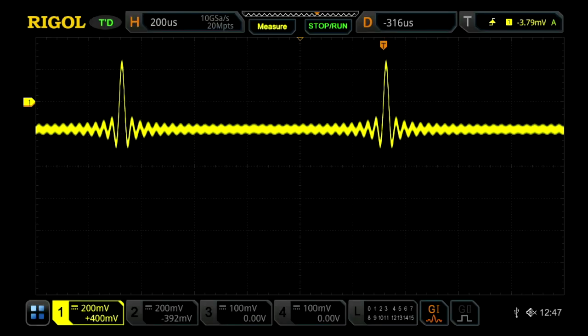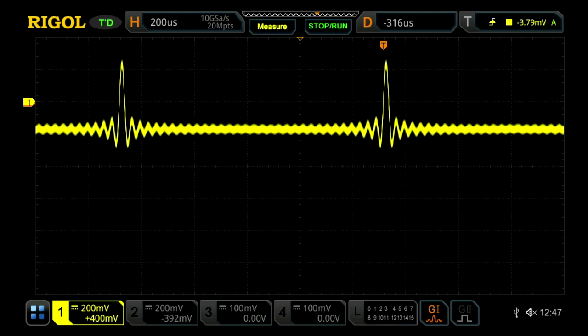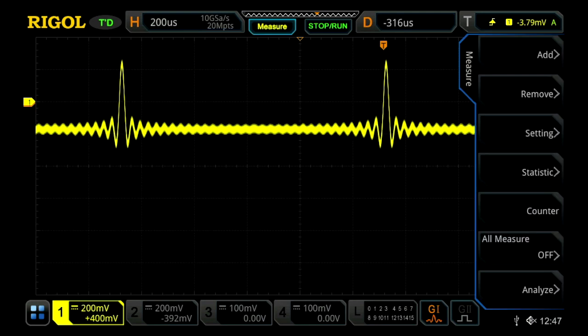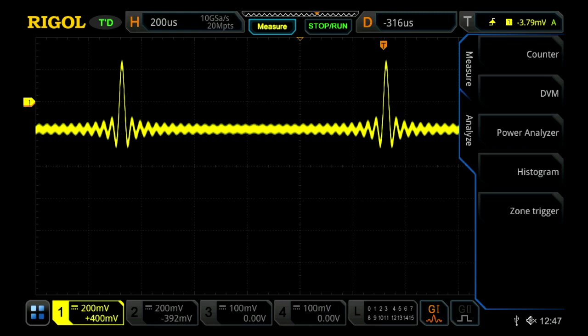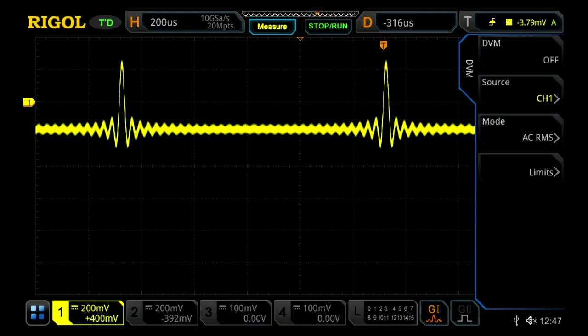These instruments come with a built-in digital voltmeter, which can allow you to easily measure the voltage of your signal. To access this, you can either do it through the quick access menu on the touch screen and then click DVM, or you can go through the measure button in the measure menu, and then go to analyze, and then press DVM as well.